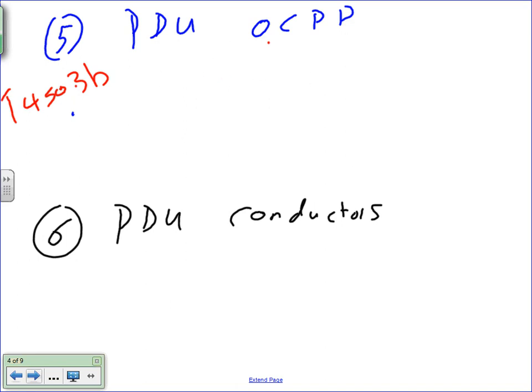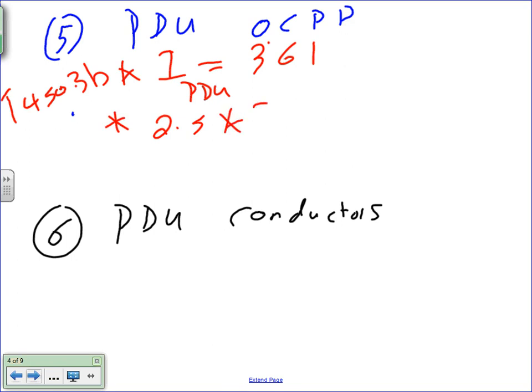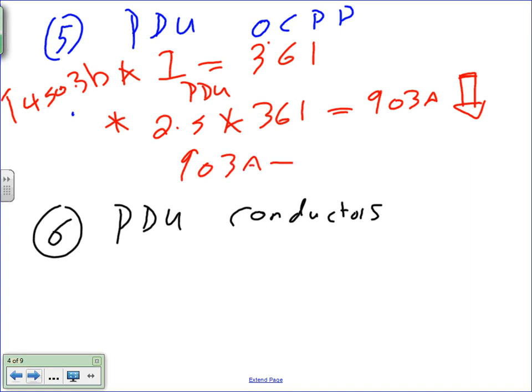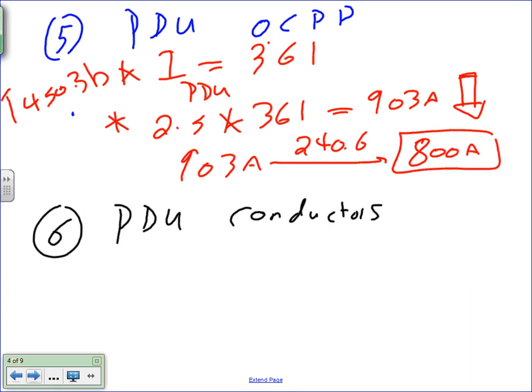I'm just going to start by first of all finding the I, equal 361. This is I for the PDU, guys. How do you find I for the PDU? Take the 300 kVA divided by the voltage. Then from there, you take the 2.5. That's step one. Step two, multiply 2.5 by 361. That will get me 903 amps. You have to go down because it doesn't allow you to go up. Then 903 amps, take this one to 240.6, and that will give you a healthy 800 amp.